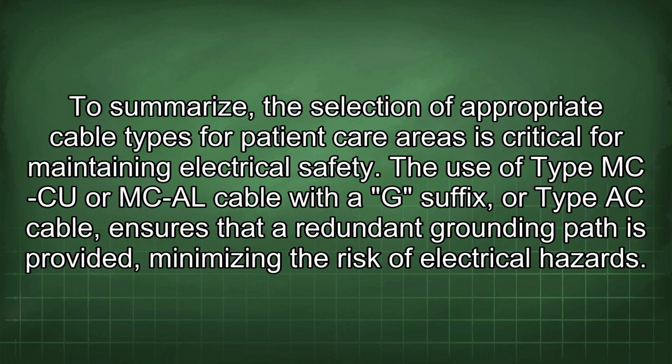To summarize, the selection of appropriate cable types for patient care areas is critical for maintaining electrical safety. The use of Type MCCU or MCAL cable with the G suffix, or Type AC cable, ensures that a redundant grounding path is provided, minimizing the risk of electrical hazards.